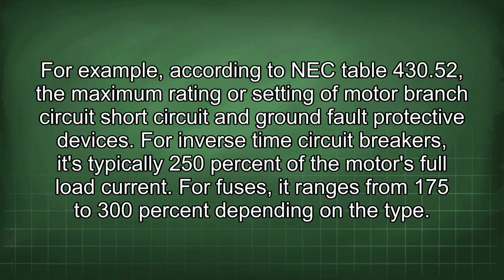For example, according to NEC Table 430.52, the maximum rating or setting of motor branch circuit, short circuit, and ground fault protective devices for inverse time circuit breakers is typically 250% of the motor's full load current. For fuses, it ranges from 175 to 300% depending on the type.